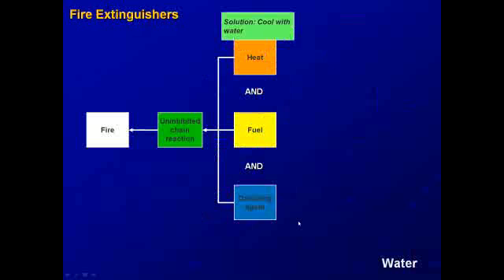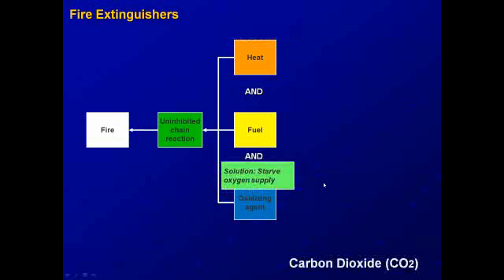There are various different ways that extinguishing methods are used to prevent or stop a fire. Water fire extinguishers act on the heat — the water cools the heat, and by reducing the heat, it stops the uninhibited chain reaction and stops the fire. Carbon dioxide fire extinguishers starve the oxygen supply, and by removing the oxidizing agent, it stops the uninhibited chain reaction and stops the fire.